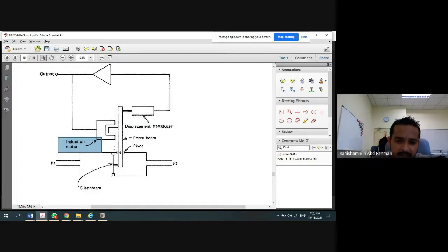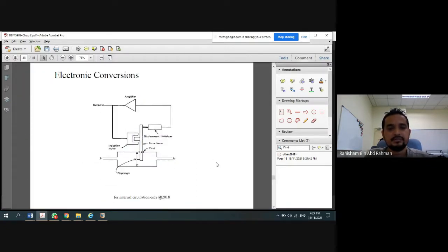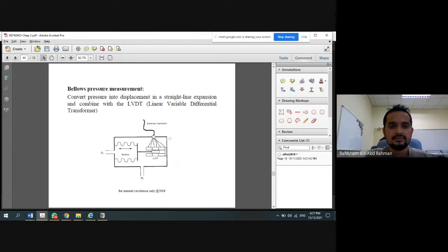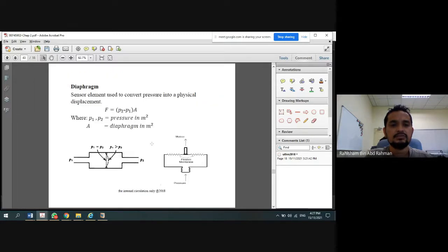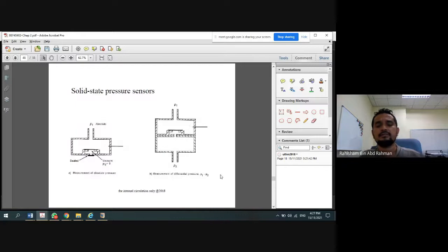So in this case, we have a pivot. Okay, we have a pivot. We have a beam here, and the movement of this beam will cause a displacement of this transducer, and also will cause the electric pulse from this movement of the magnet, and then that will be triggered to the output in terms of the display. Okay, the fundamental is just the same. A movement of this membrane, called bellows, will depend on each application to be used. Sometimes we want to use the electronic conversion, sometimes we want to use the LVDT. In some cases we may need to use this kind of simple mechanical movement. It depends on the application. It directly reflects to the sensitivity, due to the range, due to the cost, economy, and safety.